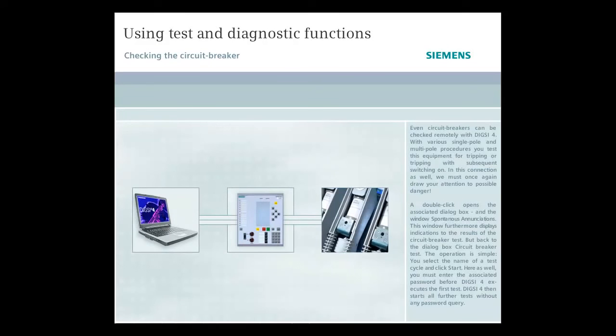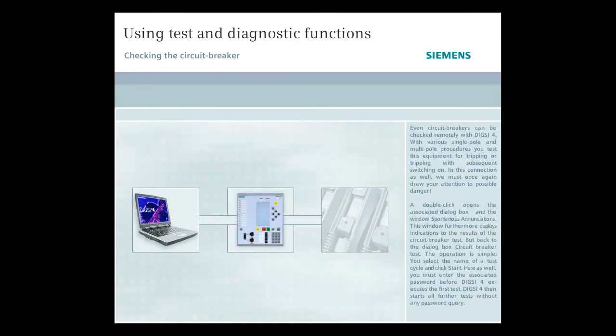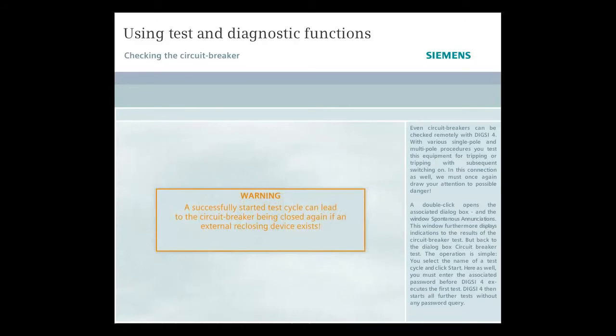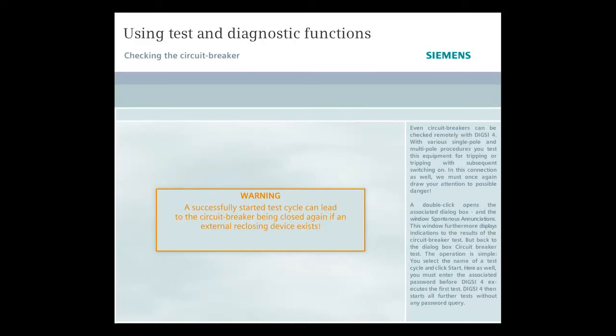Even circuit breakers can be checked remotely with DIGSI 4. With various single pole and multi-pole procedures, you test this equipment for tripping or tripping with subsequent switching on. In this connection as well, we must once again draw your attention to possible danger. A successfully started test cycle can lead to the circuit breaker being closed again if an external reclosing device exists.